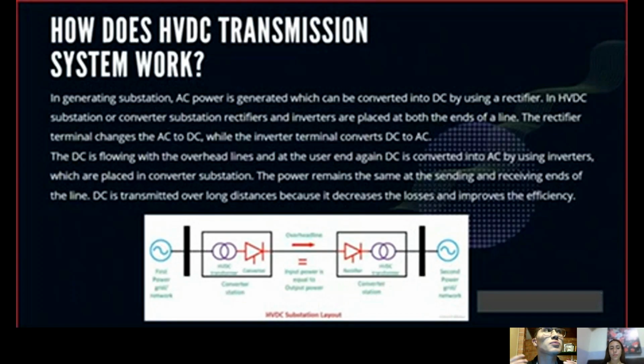In the generating substation, AC power is generated, which can be converted into DC by using a rectifier in the HVDC substation, or converting substation. Rectifiers and inverters are placed at both ends of the line. The rectifier terminal changes the AC to DC, while the inverter terminal converts DC to AC. The DC is flowing through the overhead lines, and at the user end, DC is again converted into AC by using inverters, which are placed in the converting substation. The power remains the same at the sending and receiving ends of the line.